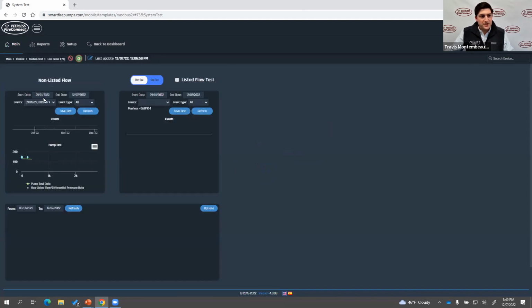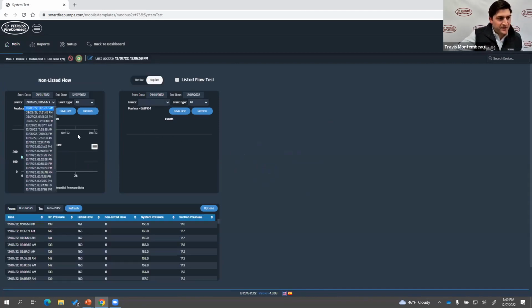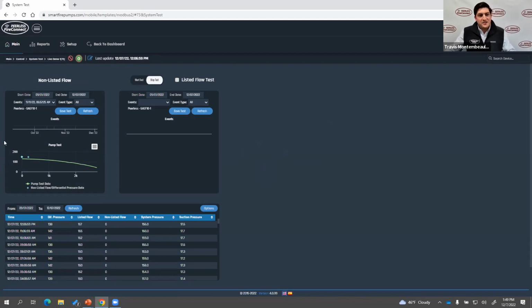System test, and we'll be somewhat brief on this one here. It was just a pretty wide range here. So I can check based on my weekly tests, and I can go through and pick a test here, and we log that information, that data, that performance over the factory curve or your field test curve, your annual field test curve. We log your pressure data and your flow data here based on what we're seeing from the system. So now you can export this curve and say, hey, I ran my test on this date. It ran for 30 minutes or plus, however long it did. Here's the curve, and you're off and running effectively from that standpoint.